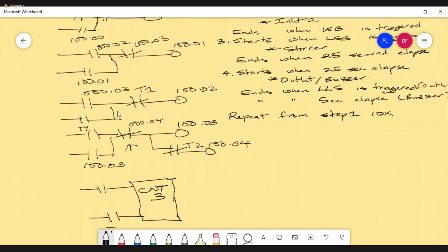And so whenever you have a program and everything seems fine, you need to look and see what is the problem. If you have labeled, the first thing you need to look and see is if you have labeled all your timers and counters properly. They must be separate.